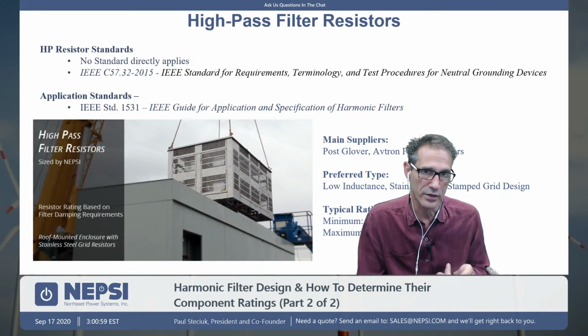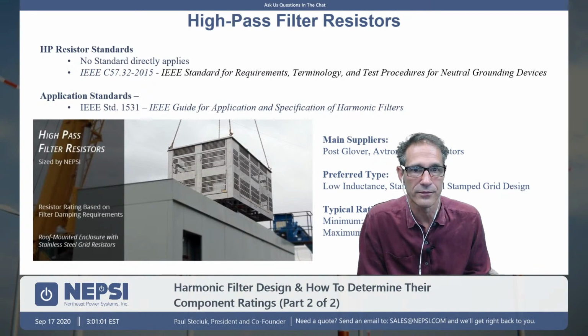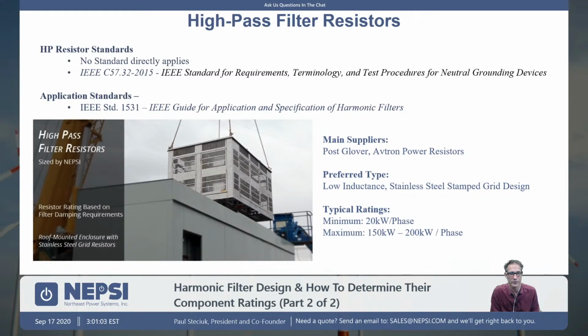So in the U.S., the primary suppliers are noted here, but Post Glover and Avtron are the key suppliers. There is a stainless steel type resistor. It's a stainless steel grid resistor. So they are exposed directly to the elements inside this box, but there's not much that can happen to it. The typical ratings are maybe minimum of 20 kW per phase, but we oftentimes see the ratings go from 150 all the way up to 200 kW per phase. So you can see why it's important to not paint that enclosure.